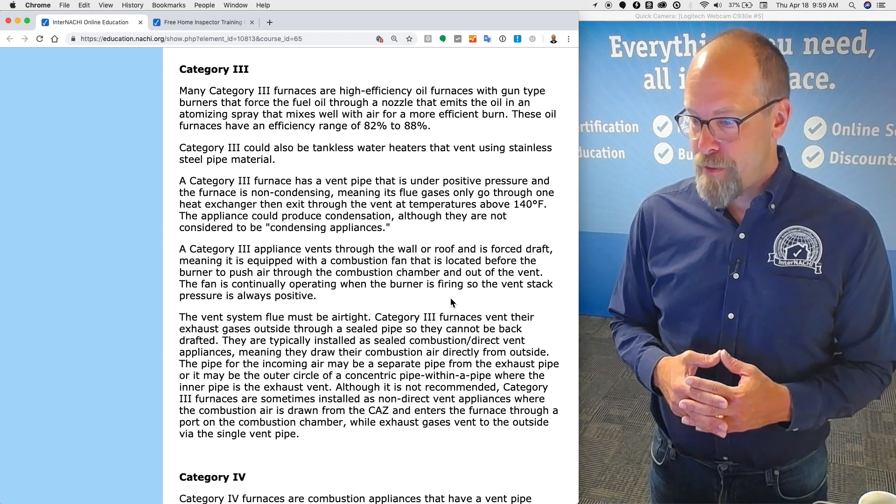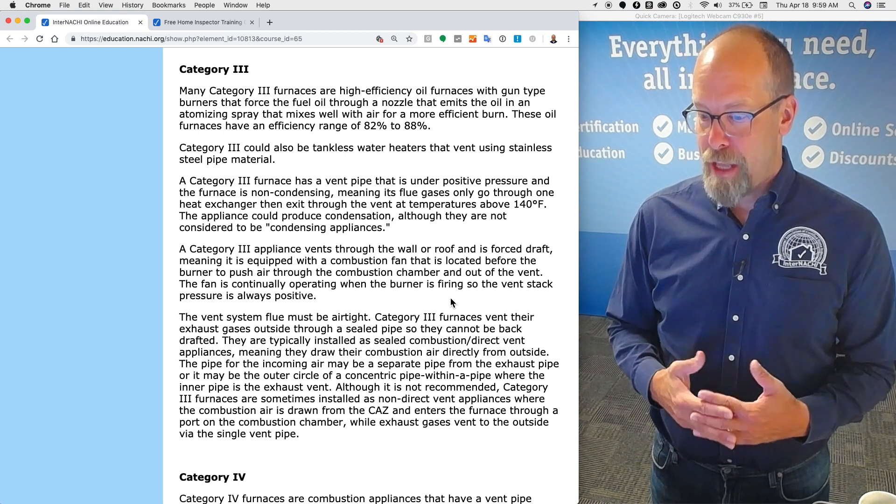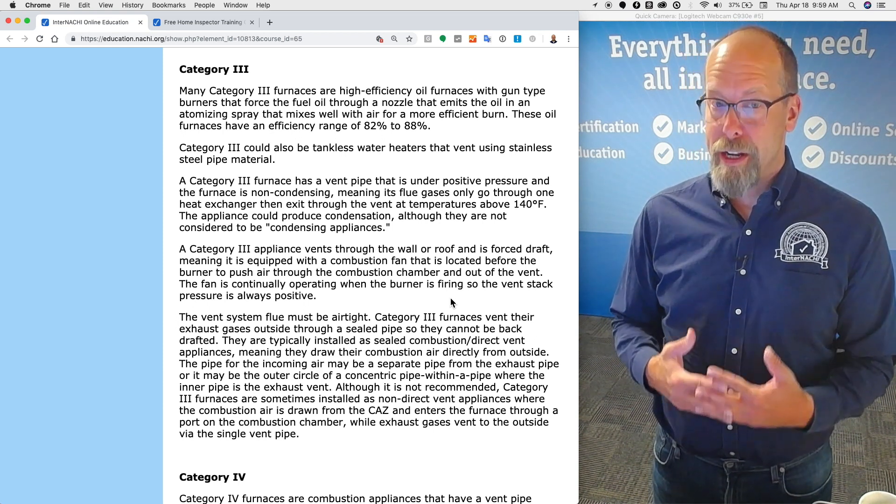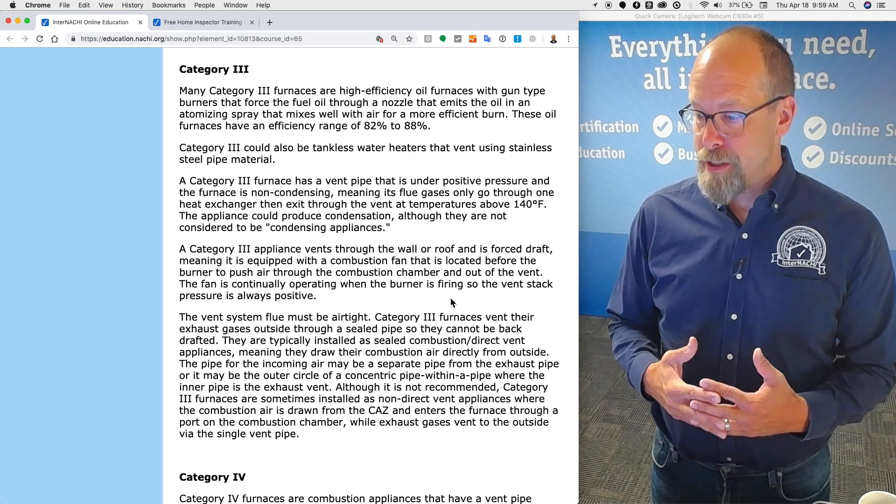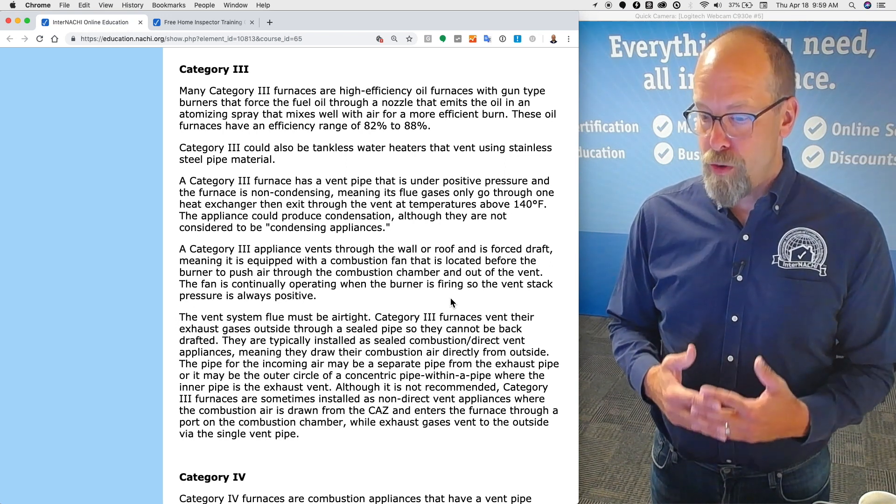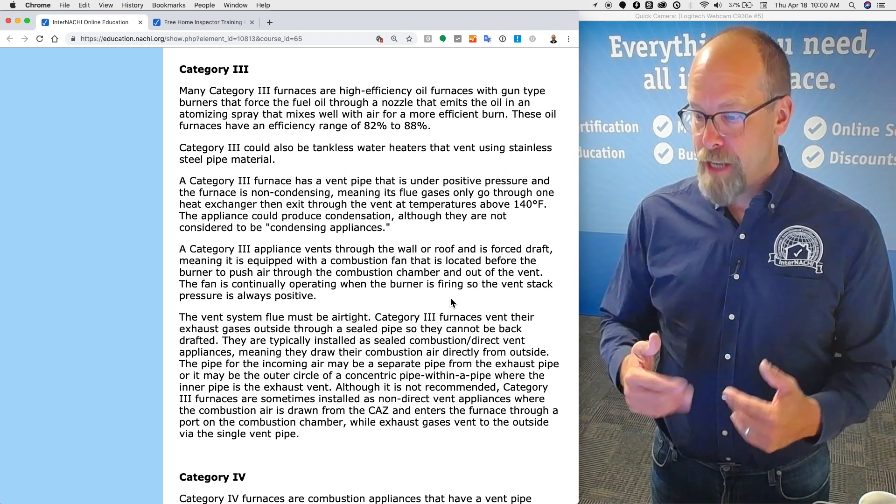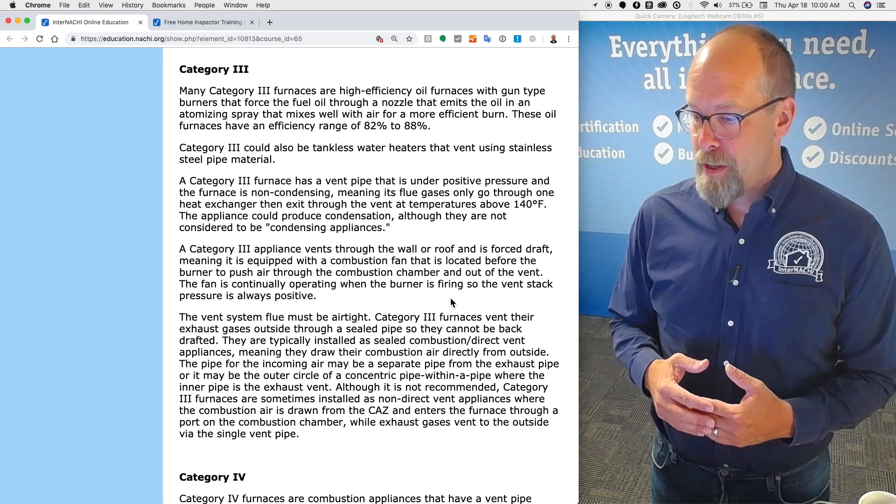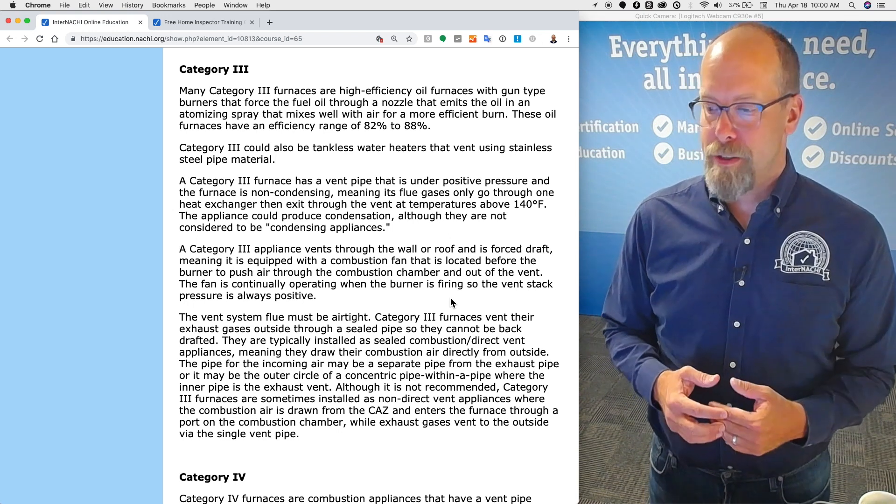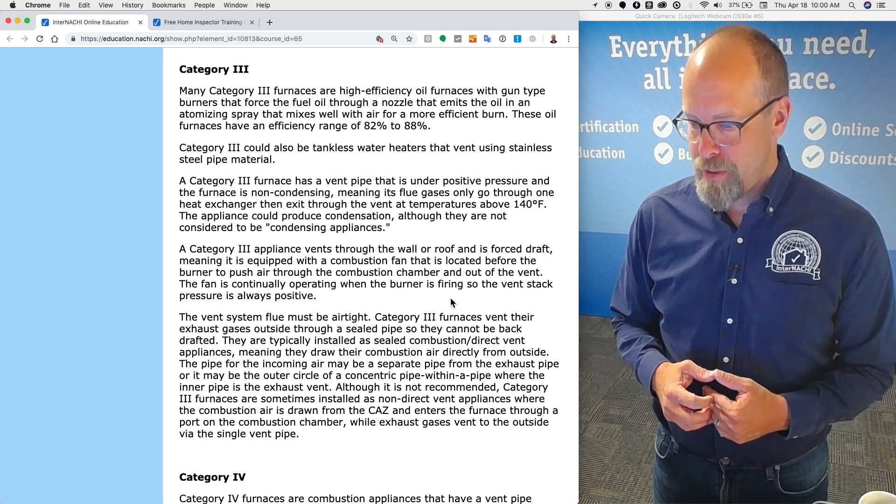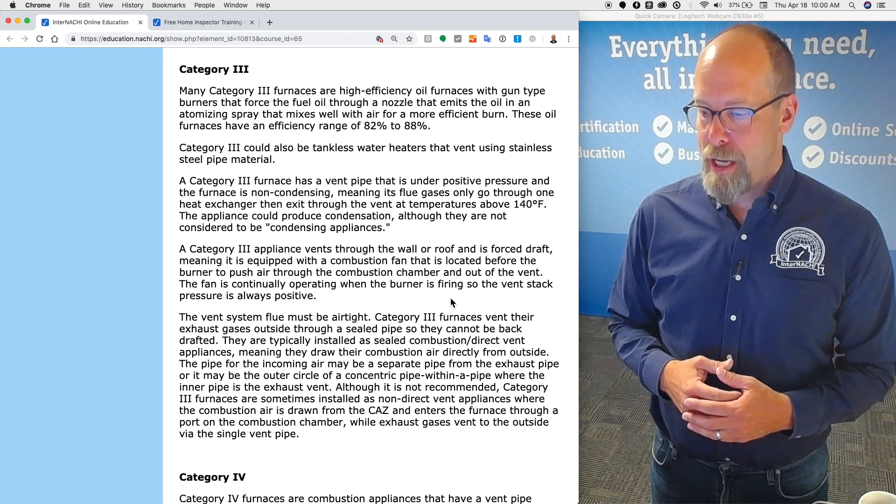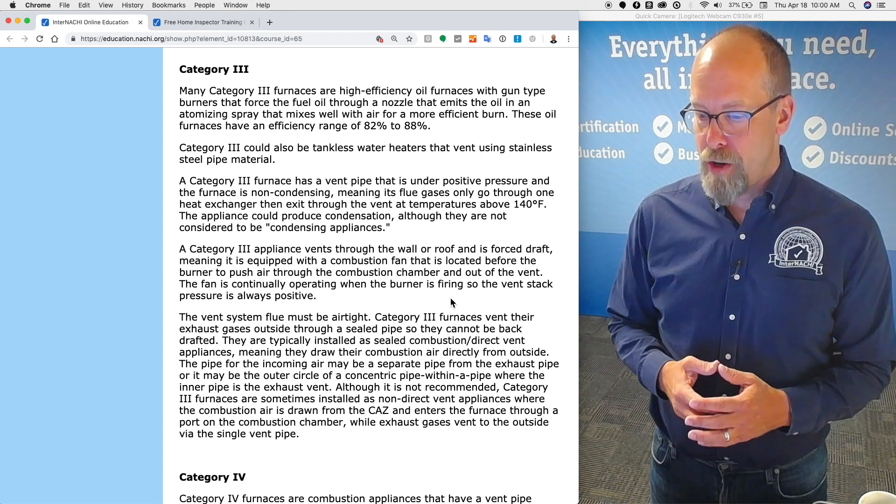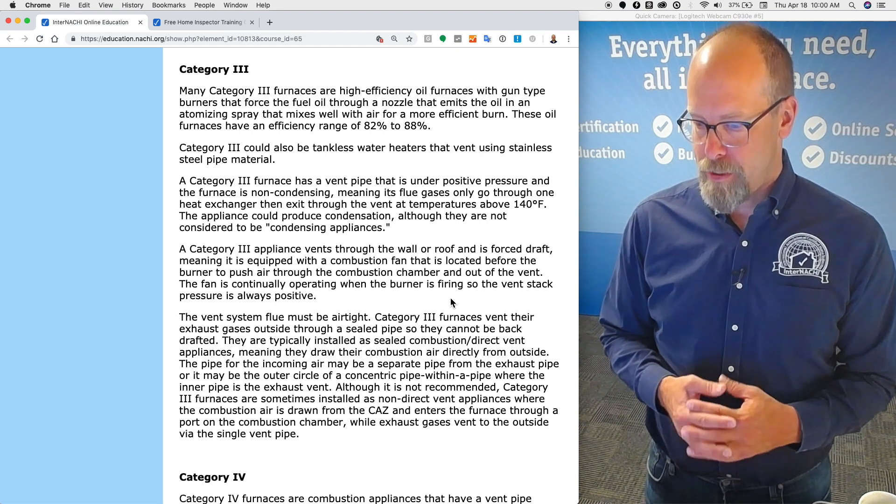A category three furnace has a vent pipe that is under positive pressure and the furnace is non-condensing, meaning its flue gases only go through one heat exchanger and then exit through the vent at temperatures above 140 degrees Fahrenheit. The appliance could produce condensation, although they are not considered to be condensing appliances.